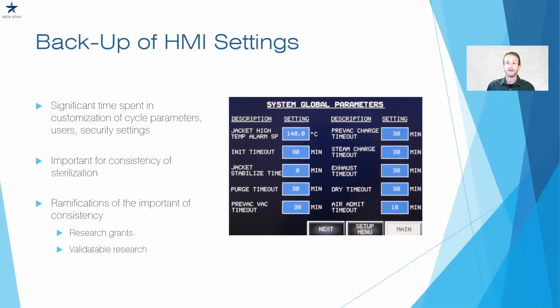IoT can help because our service team, or any other manufacturer service team that uses this type of technology, can create a backup file of all the global parameters completed at equipment startup, installation, and training, or later on if the facility receives new grants for new research and needs to add different cycle parameters. The service team can go in and create backup files of those systems. So if there's an issue with the HMI, all those files are backed up, and you cut down a lot of time that would be spent redoing those system global or cycle parameters if you lose them for any reason.